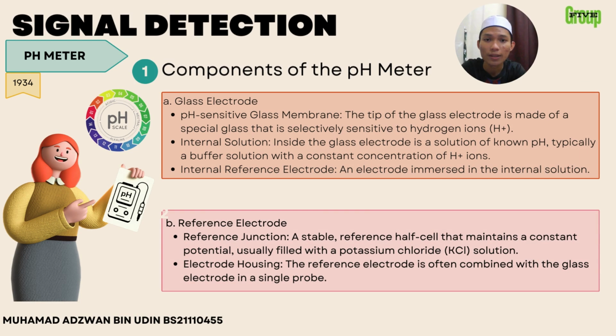The signal detection mechanism in a pH meter involves converting the chemical information related to the hydrogen ion concentration in a solution into an electrical signal. Here's a detailed explanation of the signal detection mechanism. First, the components of the pH meter, starting with the glass electrode. The pH-sensitive glass membrane: the tip of the glass electrode is made of a special glass that is selectively sensitive to hydrogen ion, H+.